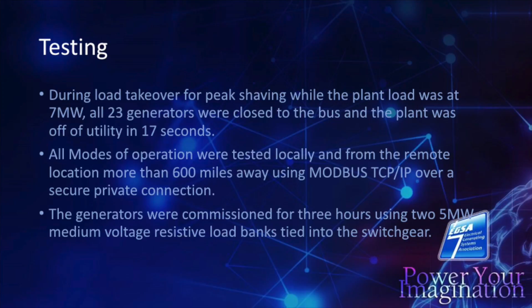And when we commissioned, we obviously didn't have enough plant load during startup, so we brought in two 5-megawatt medium voltage resistive load banks to assist with this. And that's when we discovered, as we were running our spinning reserve levels, that really helped to set the levels. Because as we were spinning reserve, they started loads that they weren't supposed to start, and we found out we didn't have enough spinning reserve.